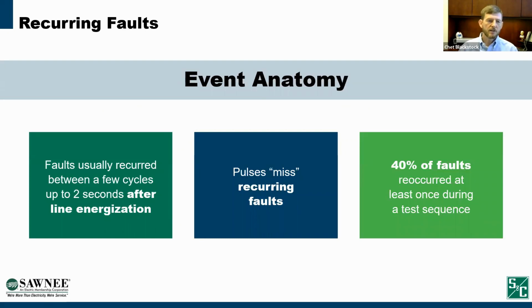So when we looked at these recurring faults, we looked at data from dozens of these faults, and we found some things in common between those faults. One was they usually recurred sometime between a few cycles and a few seconds after the line was energized. And what we saw was a majority of those recurred within 2 seconds of the line being energized. The next was that it wasn't that the pulse was malfunctioning, it was just that no fault existed when it first pulsed. And finally, we saw that almost 40% of the faults on our system reoccurred at least once during a test sequence.